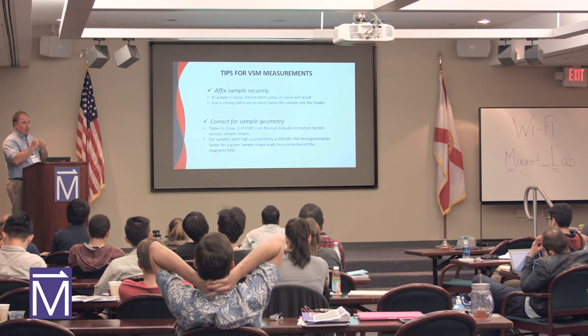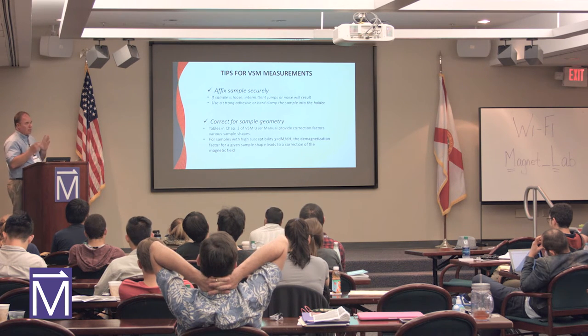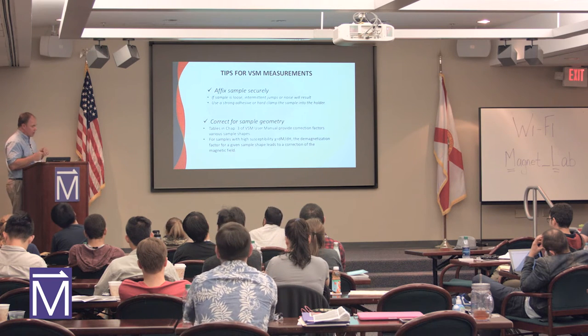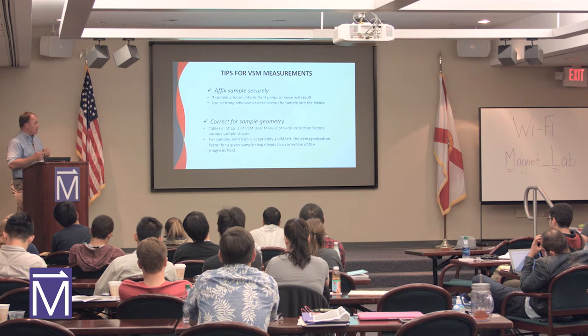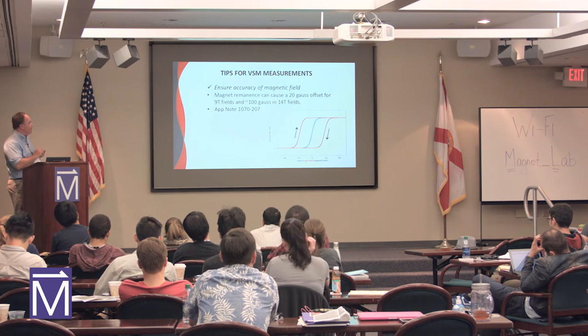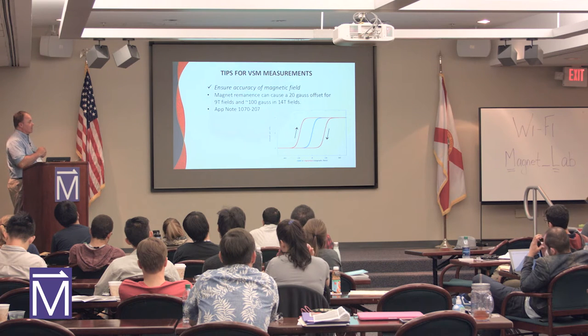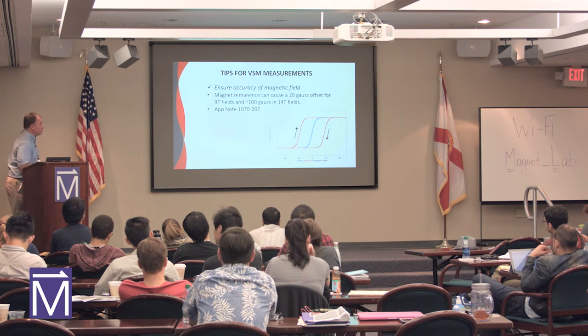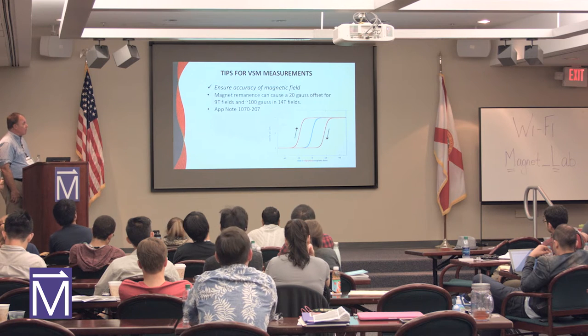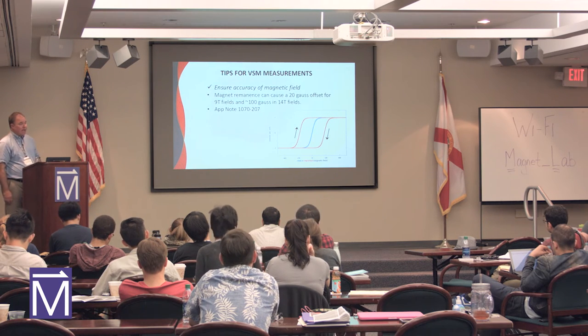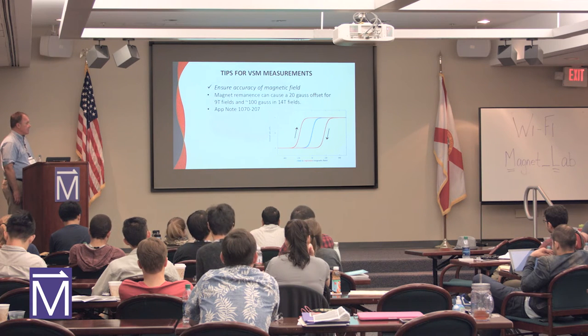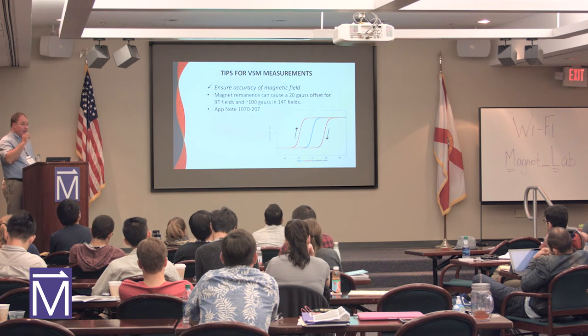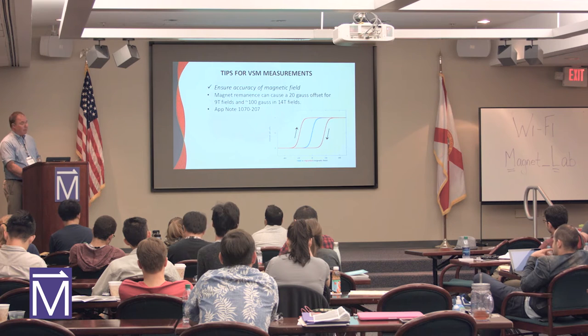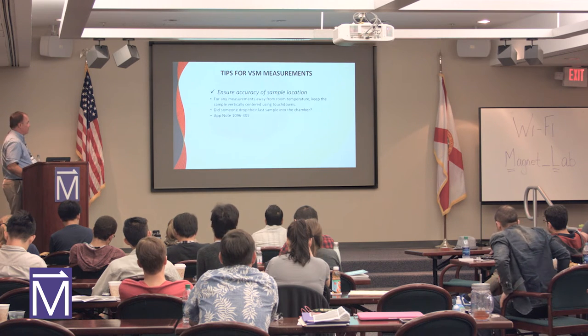Sample geometry. The measurement assumes some sample geometries, and you can correct for those factors. We've got a nice table in the user manual that talks about shape factors for the sample material. Remnant field. Superconducting magnets have a remnant field, and there are a couple of tricks you can do to minimize it. It's about 20 Gauss in the 9 Tesla system and 100 Gauss in the 14 Tesla system. So if you're making measurements at low magnetic fields, you have to worry about the remnant field, because that may dominate your experiment. And we have a nice app note on that.